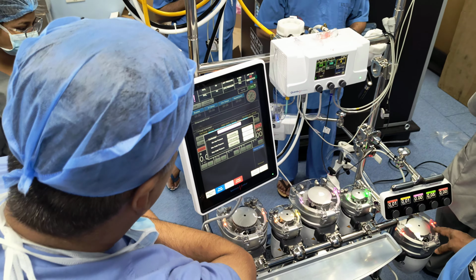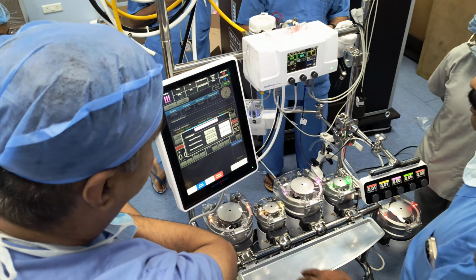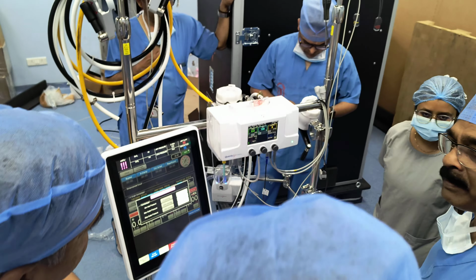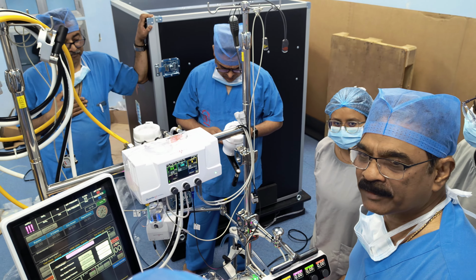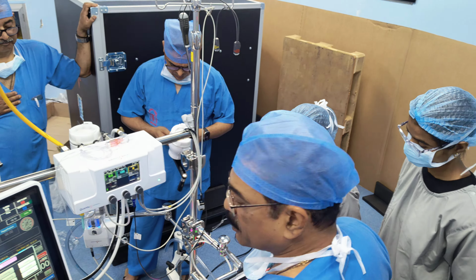What we do is we have linked it to a positive pressure. So even if your arterial pump is off and not moving, you want to start cardioplegia. If it is connected to the arterial line, obviously there is a positive pressure. So we say minimum inlet pressure 5 as a safety. However, if you don't want it, you can disable it. This is a safety.